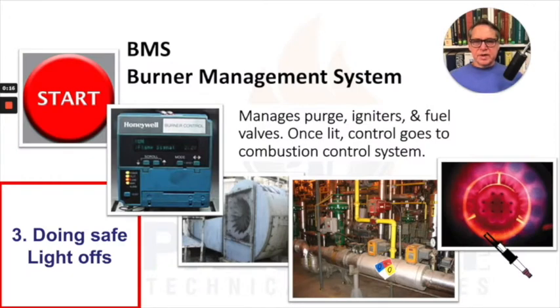So here's kind of a sequence of how things happen. And it all starts with us engaging the burner management system. So we hit the start button. The burner management system senses that we're trying to start. It initiates looking at a series of what we call permissives, and we'll discuss that in the next slide. If everything's ready in a startup condition, then a fan starts and we start to purge the system.